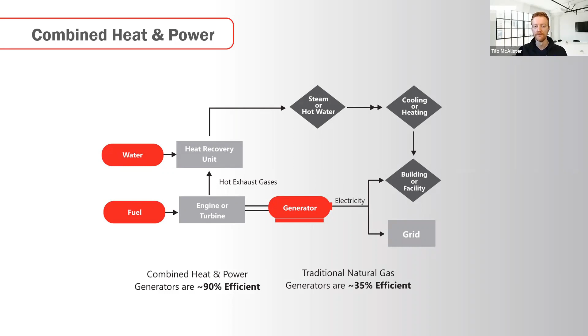This is a 140 kilowatt unit that sits on the rooftop of a condo building in Toronto, and it runs 24/7. It's sized to the base load demand of the building so that we'll never be exporting any electricity to the grid, and the generator can run at 100% of its capacity, its most efficient power band, 24/7, and supply electricity to the customer at a lower cost than they can buy it from the utility company. Then the heat is recovered from the exhaust and the coolant in the form of hot water, which is used to preheat the water going into their existing boiler system.